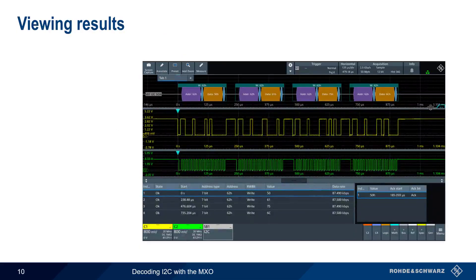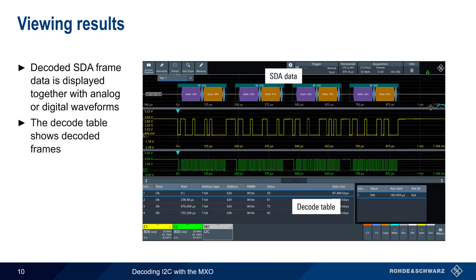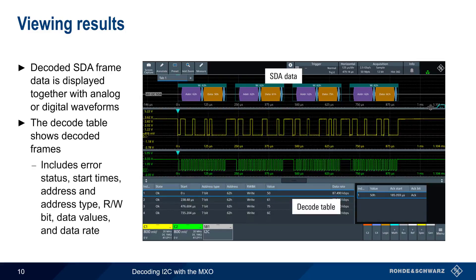After parameters have been configured and acquisition started, decoded SDA data is shown on the screen along with the analog or digital waveforms. The decoded data can also be displayed in the decode table at the bottom of the screen. The decode table includes information such as the frame state, start times, address type and value, read/write bit, etc. All of this information is updated in real-time.